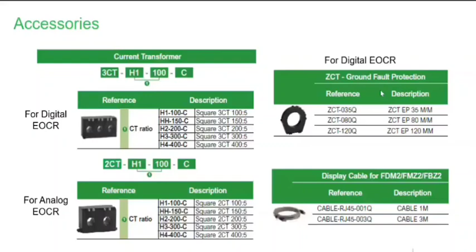Yeah, thank you. So if you want to use, as I mentioned, this is tested for up to 400 ampere, you can use this three-phase CT along with this product. There is a CBCT available in our portfolio. There are two variants available in this. One is a window hole type and one is a bottom hole type. In the window hole type, you will see there is a three-phase CT which is installed on the product's upper side, and there is a pass-through design in the bottom hole. Generally, the pass-through design becomes easy for customers from a wiring point of view. So we recommend going with the bottom hole design.